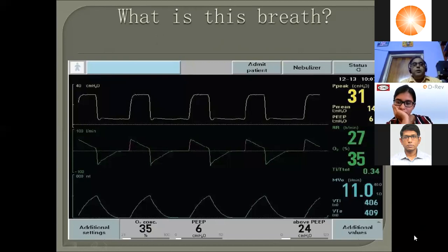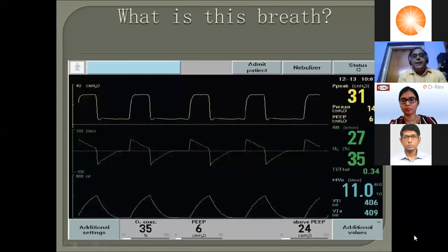What is happening here? So this is a pressure time scalar and it is a square window. So it is something to do with, it is pressure controlled. But look at this flow time scalar. None of the flow curves are actually touching the baseline. None of them. Okay. So it looks like all of them are supported breaths. One other thing is, remember, all supported breaths have to be patient triggered. All patient supported breaths have to be patient triggered. That is not very obvious here, but they are often color coded. So if there was a color code, you could see that all of them are triggered breaths. So then basically all the breaths here are supported breaths. So what mode is it? It is CPAP PS. Yeah, you only have supported breaths and nothing else. Next one, please.